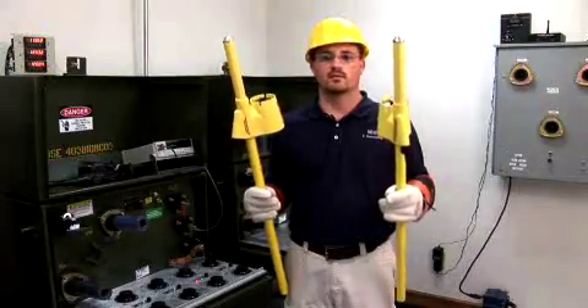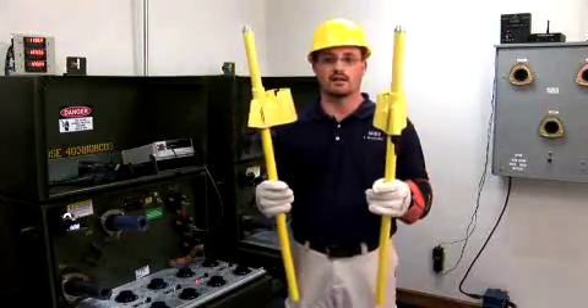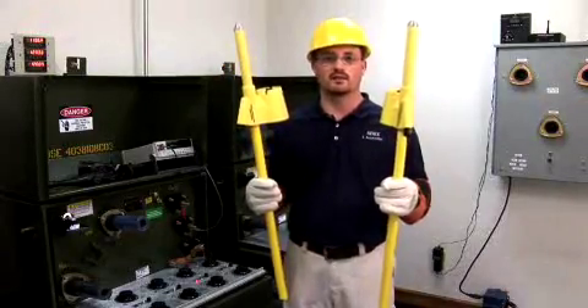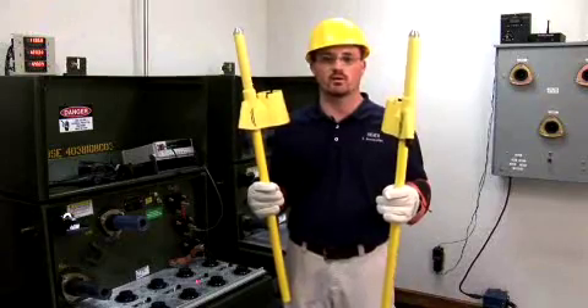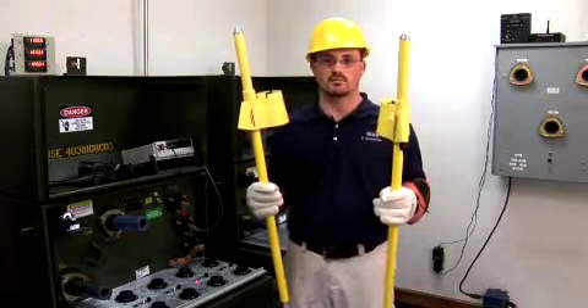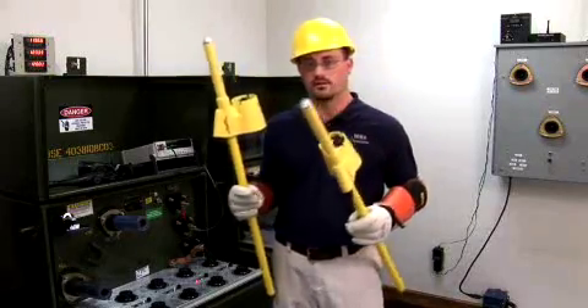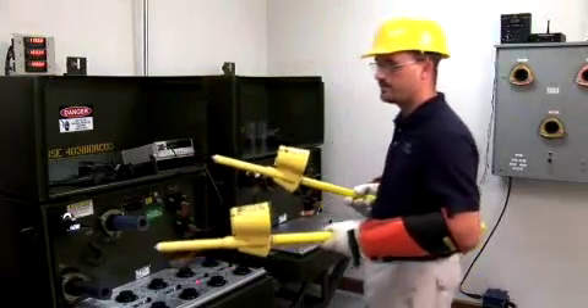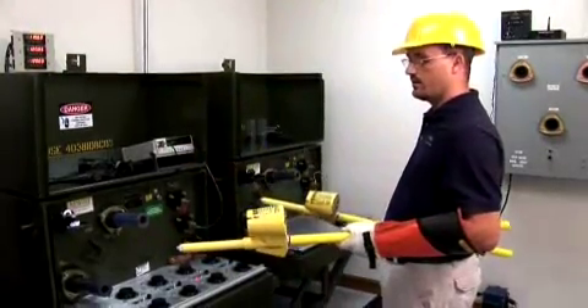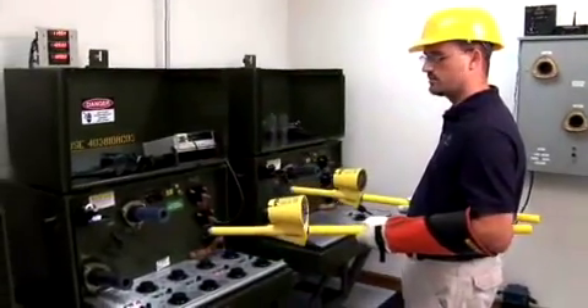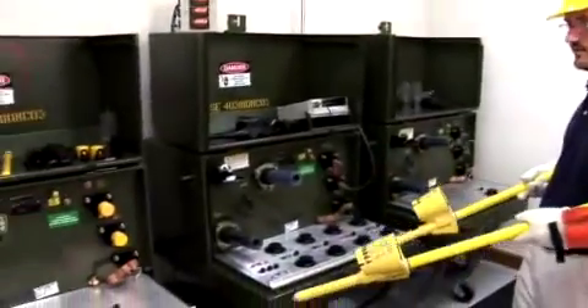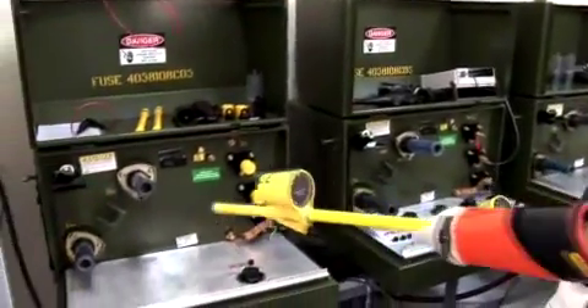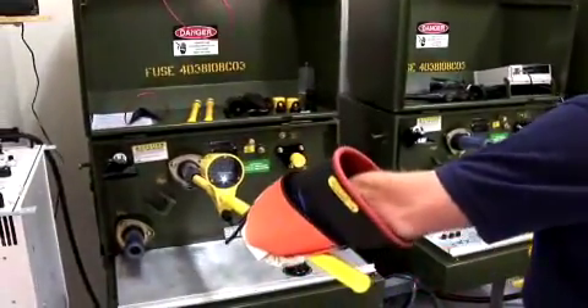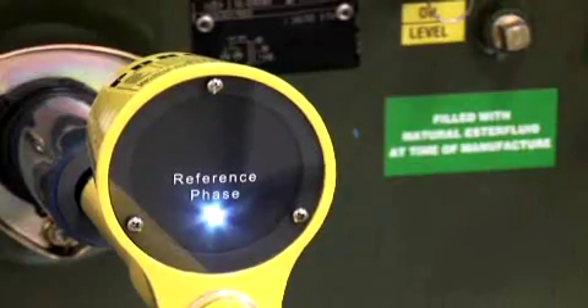The PD800W can be used for phasing any voltage, whether it be secondary, capacitive test points, primary, or transmission voltage. We're going to demonstrate that here at our facility. We have three single-phase pad mount transformers. We have A phase, B phase, C phase. We'll attach our reference probe to the first transformer. The next phase is B phase.